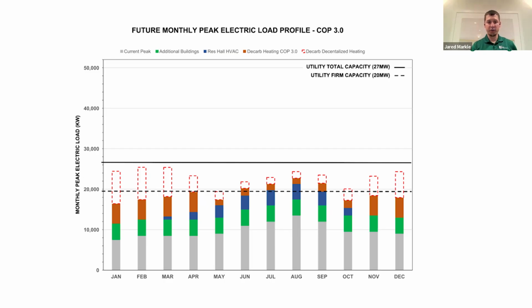Since we were already over the firm capacity of the system, shown as the dashed black line, firm capacity means the capacity you can reliably count on in the event of losing one item in what you're looking at. In this case, it's losing your largest feeder in a set of feeders. It could be your largest boiler in a set of boilers, or largest chiller in a set of chillers, but that's generally how you look at firm capacity in an overall system.